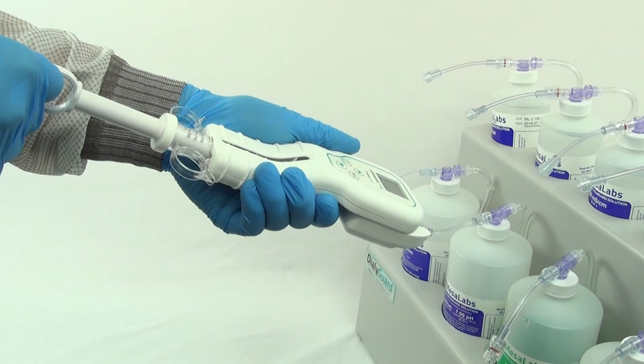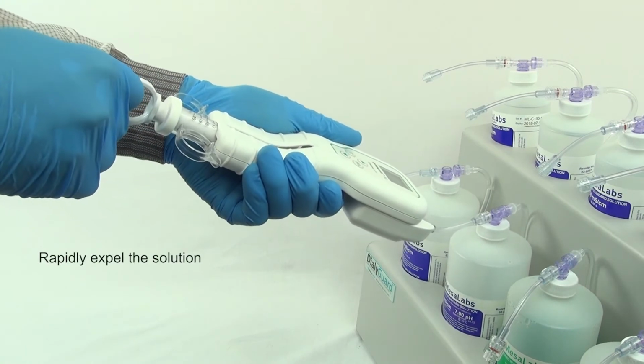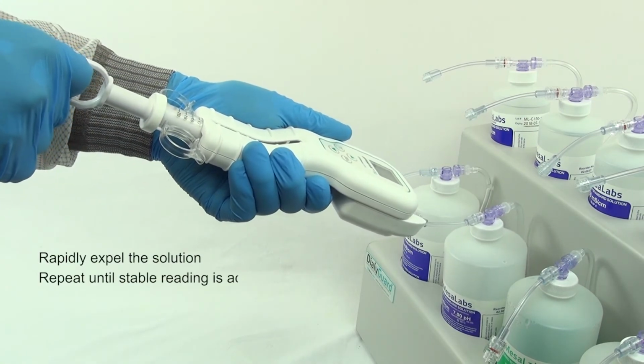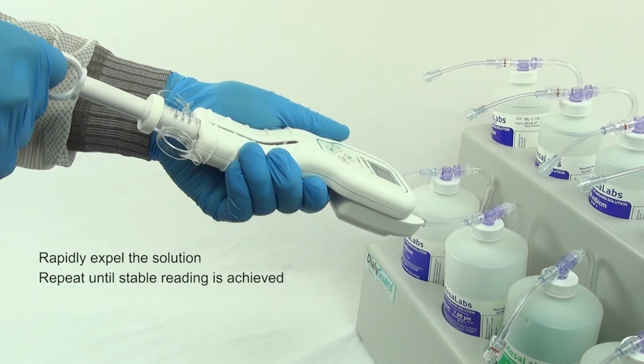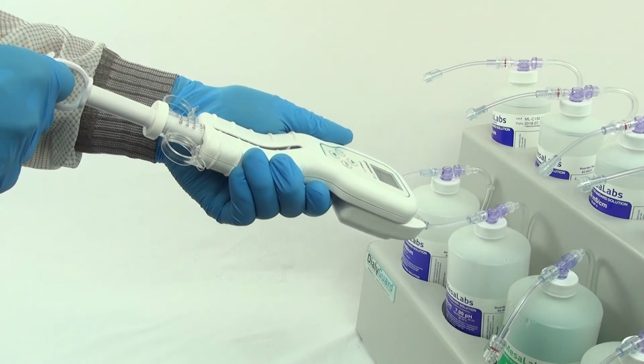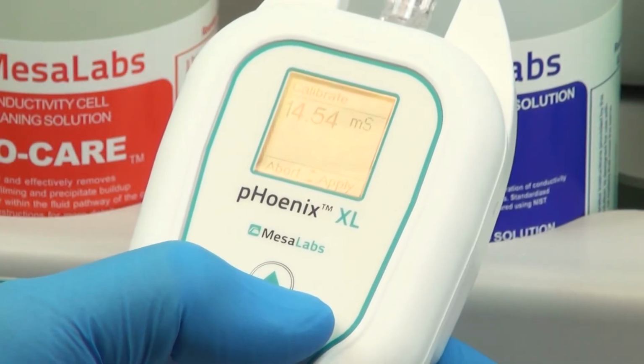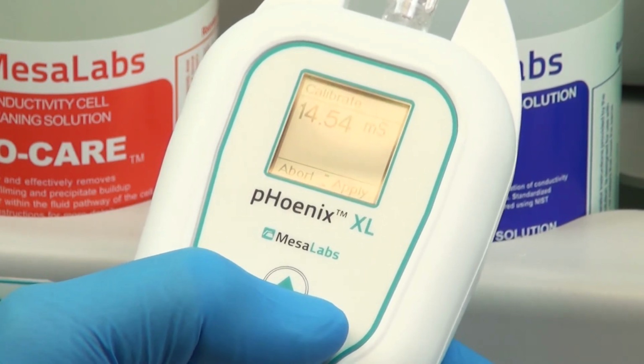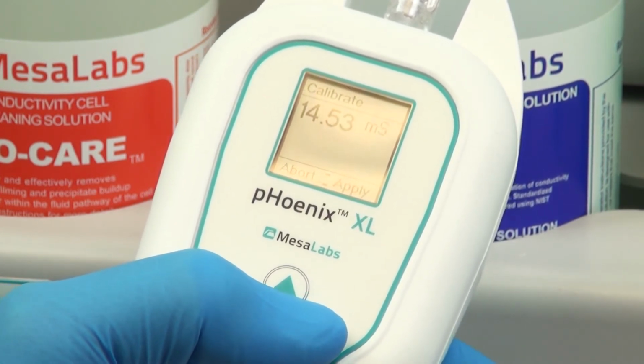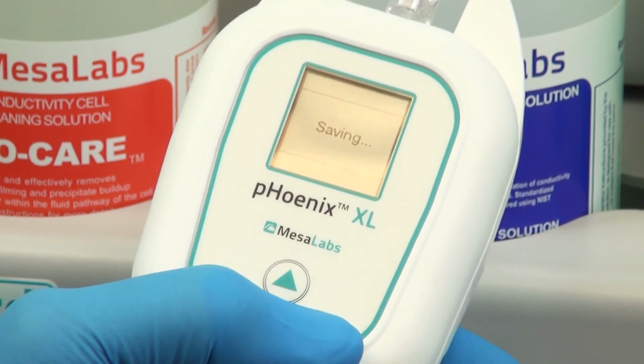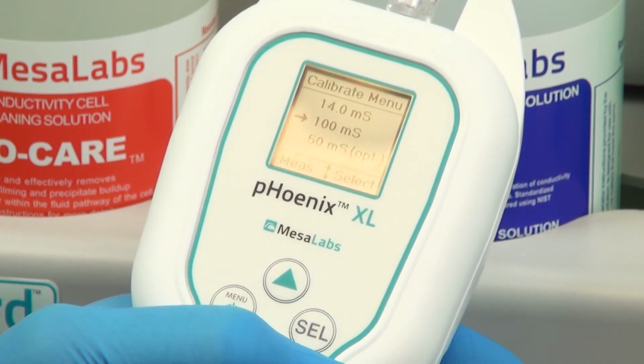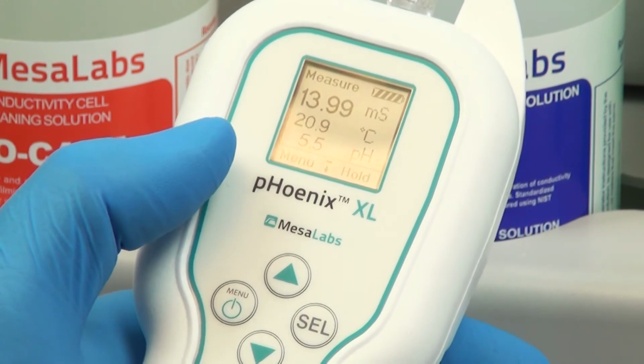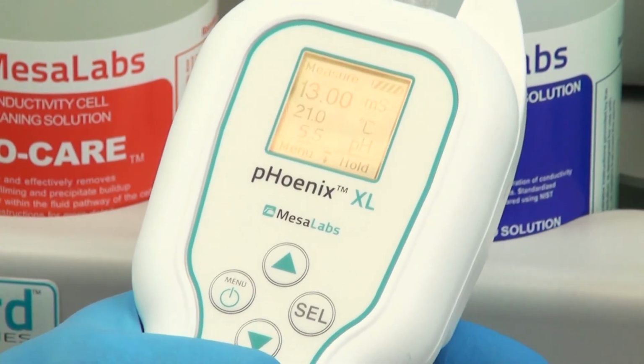Keep your eye on the display, looking for a stable reading. When you have reached 10 milliliters, rapidly expel the solution and repeat the pull to 10 milliliters until you obtain a stable reading. When you have maintained a stable reading for 2 to 4 seconds, press the select button to save your calibration value. Your meter will automatically adjust the numbers for you, so there is no need for a manual adjustment. The pHoenix XL meter will not adjust the reading when pressing the up or down arrows.